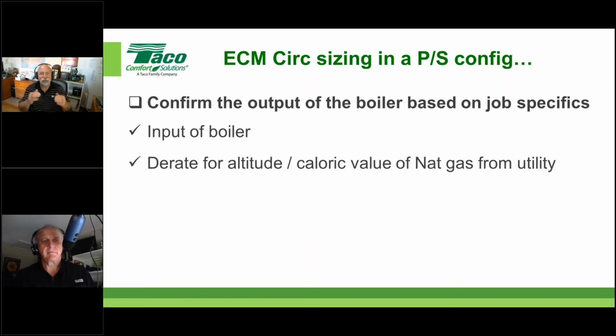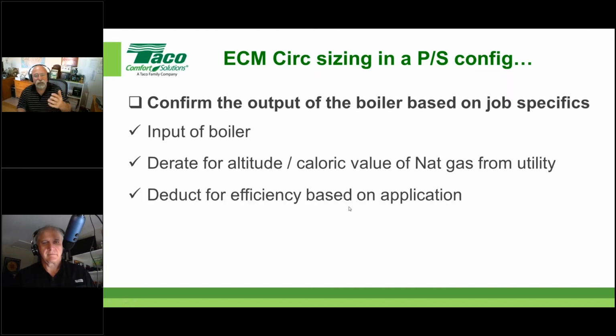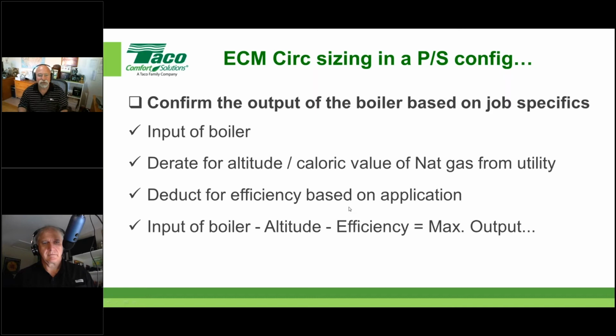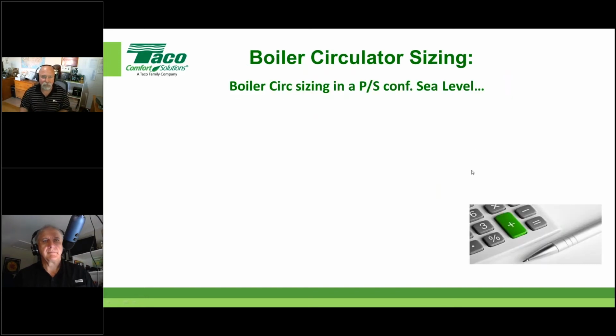Okay, you have to derate for altitude, you have to derate for efficiency, and then you size that circulator based on that. You take the input of the boiler, minus anything for derate on altitude, minus your efficiency, and that would be your maximum output. And you size the circulator for safety's sake on that. Actually, in some more advanced trainings, I will show you how you can shave that off a little bit as well. So let's do something real quick.